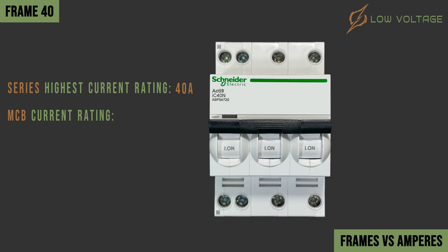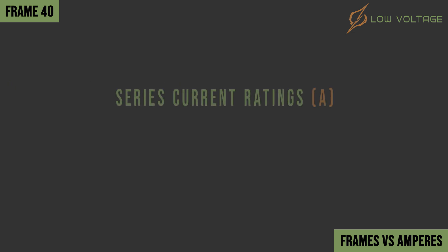In this example, the series code is a designation to identify the type of breaker and frame size. The code indicates that this series has a maximum current rating of 40 amperes, and the rating of this MCB is 20 amperes. Generally speaking, Frame 40 has a current rating between 1 ampere reaching a maximum rating of 40 amperes. Each manufacturer has its own current rating series, so current rating values may vary between them.